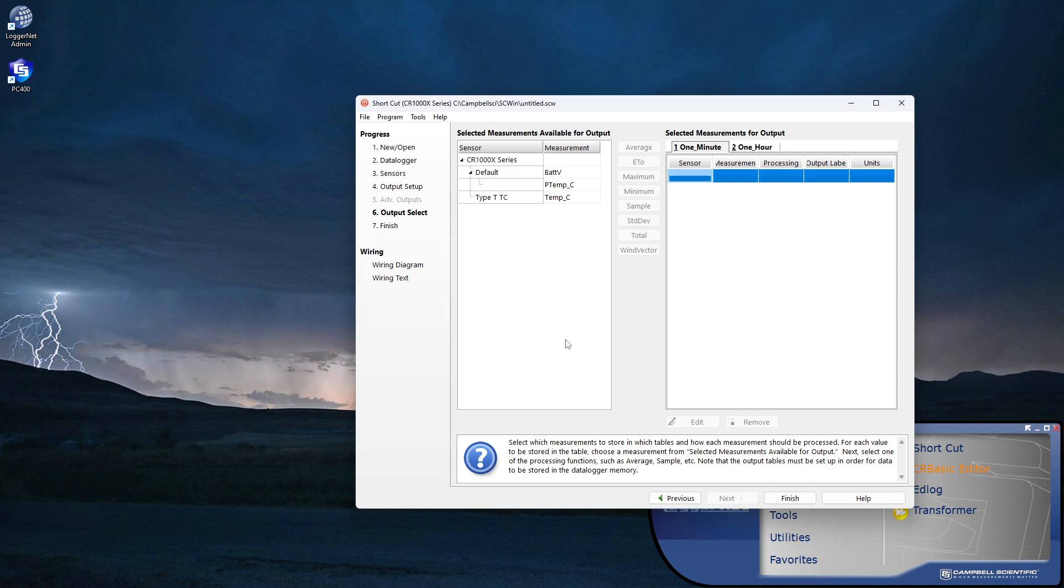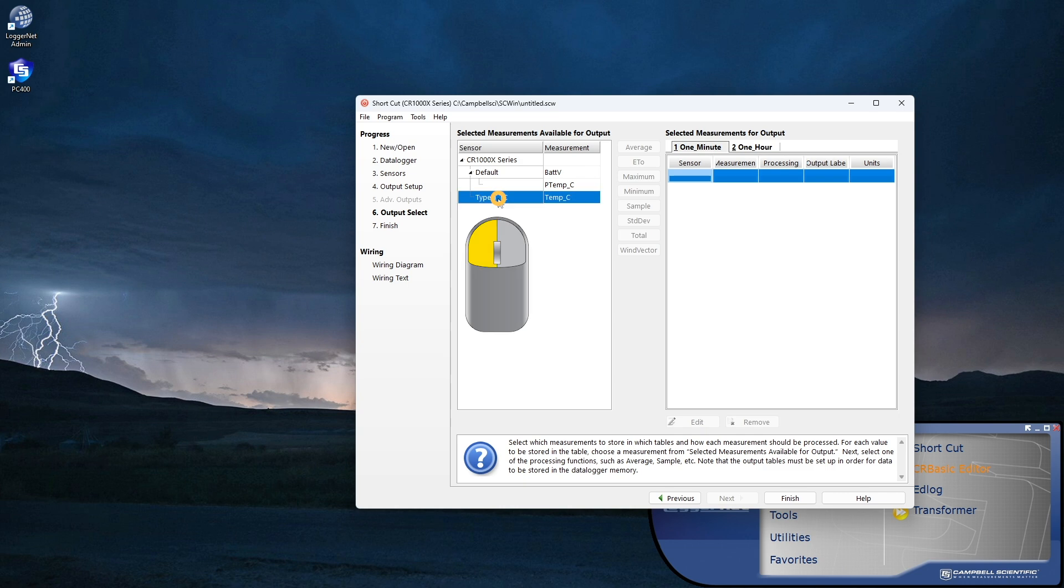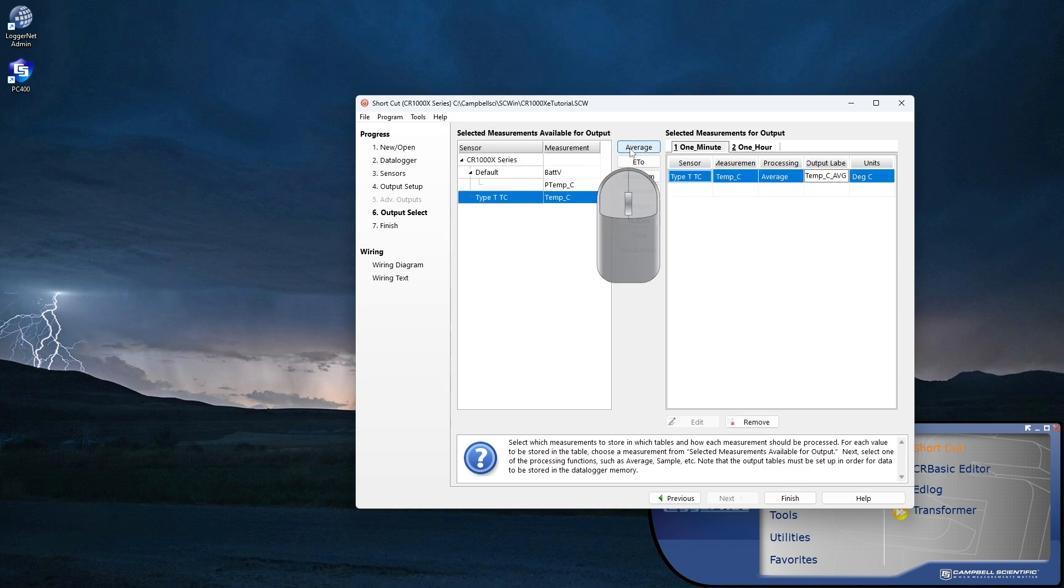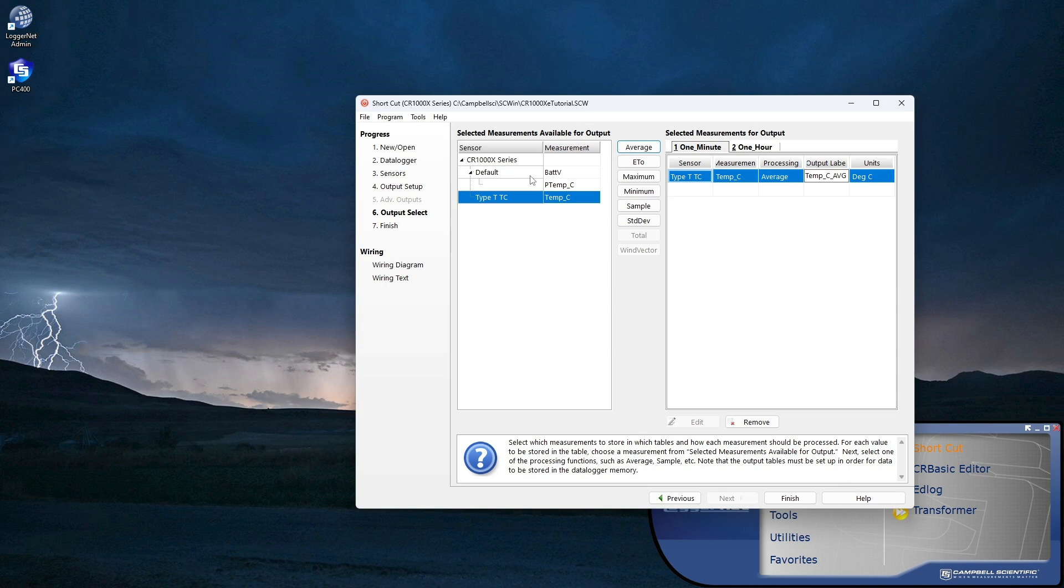I'll add measurements with processing to the table. Each minute, I'll have the data logger store the average air temperature. Since the data logger is taking one second measurements, this will be an average of 60 discrete measurements. Other measurements and processing are added in the same way.